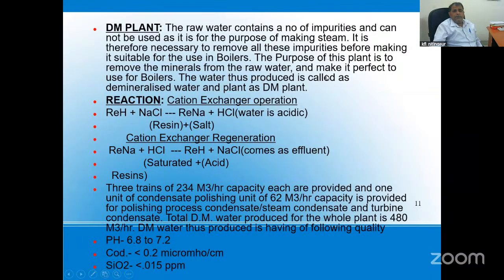So the main purpose of the DM plant is to make water suitable for the use of the boiler. Why? Because minerals present in the raw water form scaling inside the boiler tubes and decrease the efficiency of the boiler. It is not only scaling; there is also corrosion and erosion inside the tube due to high temperature. Minerals attack the tubes and they get corroded. Boiler tube corrosion and erosion means damage of tubes.